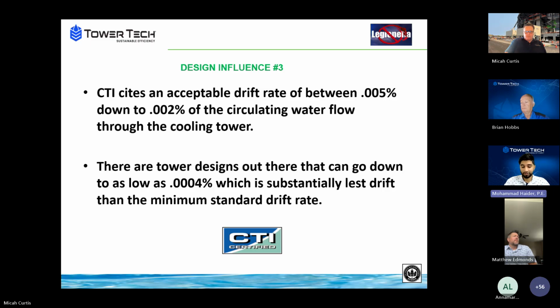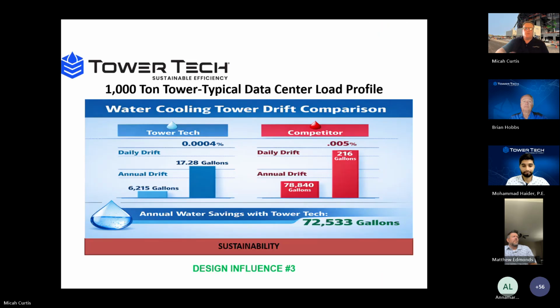And when you get into those small numbers, that's when you're talking about drastically reducing the amount of water that you're proliferating into the surrounding environment. So if you do have Legionella in the system, which we've discussed, you almost always do, the lower your drift rate is, the significantly less amount of actual water you're putting into the surrounding environment.